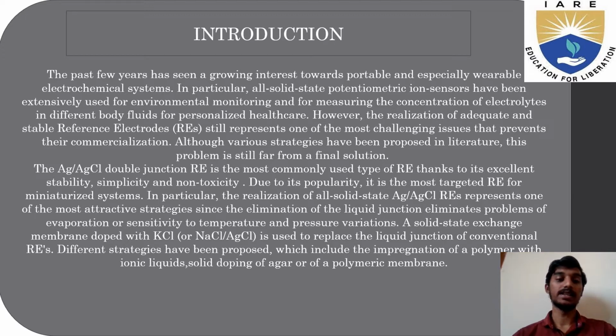The Ag/AgCl double junction RE is the most commonly used type of RE thanks to its excellent stability, simplicity, and non-toxic nature. Due to its popularity, it is the most targeted RE for miniaturized systems. In particular, the realization of all solid-state Ag/AgCl REs represents one of the most attractive strategies since it eliminates the liquid junction and the problems of evaporation or sensitivity to temperature and pressure variations.